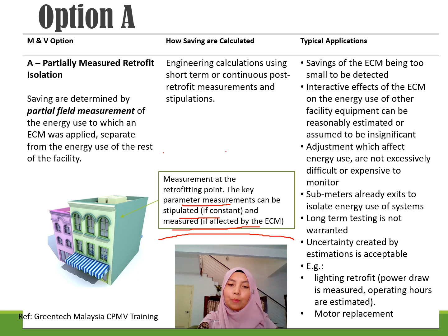it's not big. So example of application, as I mentioned earlier, lighting replacement to a more efficient lighting system, where the power draw you measure and the operation hour, if it's constant, then you can stipulate. Other application, motor replacement, where you replace an old motor with an efficient motor, so the power draw changes, so you measure the power draw, and if the operation of the motor is constant, then you can estimate or stipulate the operation hour of the motor. So option A is usually used for replacing a lighting system with a more efficient lighting system.